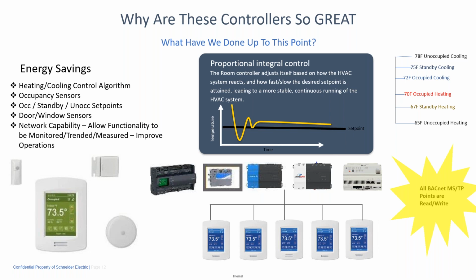You can have a built-in occupancy sensor in. You can hardwire an occupancy sensor, or you can use the wireless ones for occupancy. Why control to the occupied set point when there's nobody in the room, right? So you can have those. And when you have that occupancy option available to you, it has 3 levels of set point, and that's kind of shown up in the upper right hand corner here.